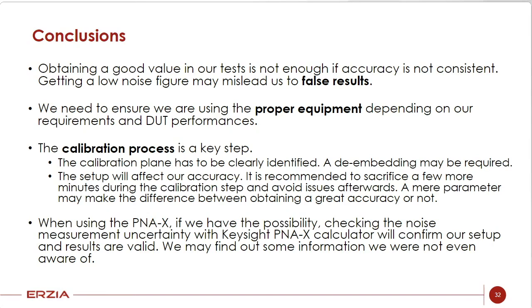So the first one is that obtaining good values in the test is not enough if the accuracy is not consistent. So values or numbers like the noise figure might mislead us to false results. We need to select proper equipment depending on our requirements and the expected performance of our device under test. And of course, the calibration process is a key step.